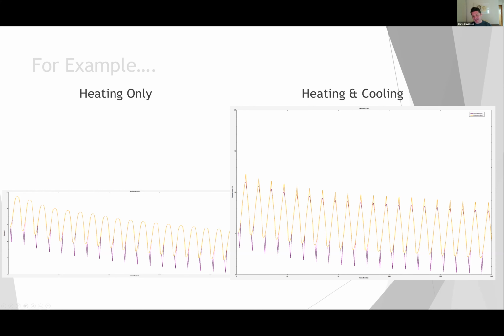It tends to a limit at about year 20, where it stops getting any colder, but that ground is depressed in temperature throughout the life of the system. And it gets up to a maximum of the undisturbed ground temperature, which is 9.8 degrees. If we look at the heating and cooling system now, you can see that during significant portions of the year, the ground loop temperature is well above that undisturbed ground temperature.